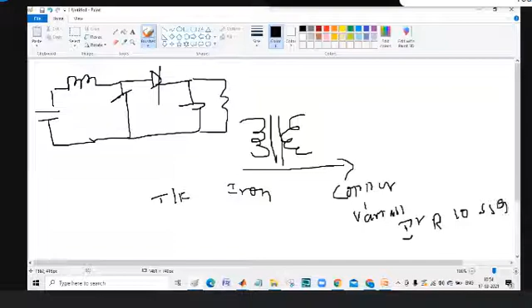Iron losses depend upon V by F only. Here frequency is constant, only voltage we are sending the power supply with. But iron losses are fixed losses, we can't change them. The I square R losses, if we are minimizing them so that they equal the iron losses or variable losses, then we can send the maximum power in this one.